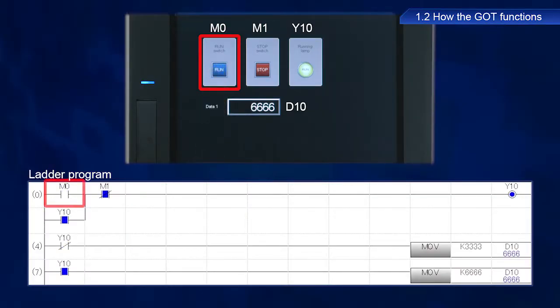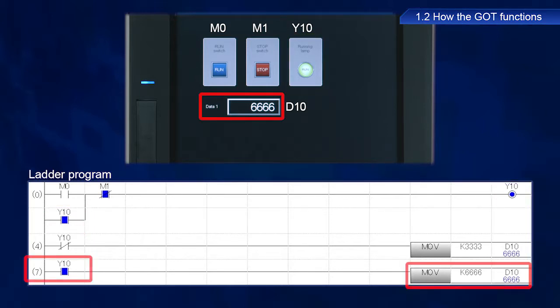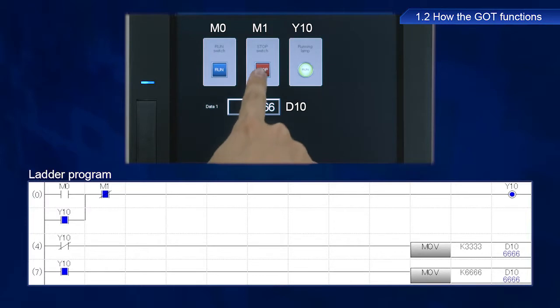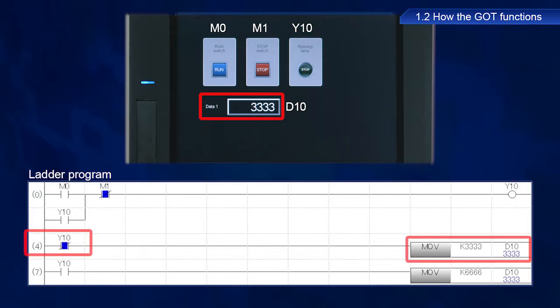Pressing the run switch triggers an input of M0, which causes the running lamp Y10 to turn on. Y10 is a self-retaining circuit, so the lamp stays on. The input of Y10 triggers a move transfer command to display a value of 6,666 in D10 for data1. Pressing the stop switch triggers an input of M1, which turns off Y10 via a normally closed contact. A value of 3,333 appears in D10 via the Y10 normally closed contact.